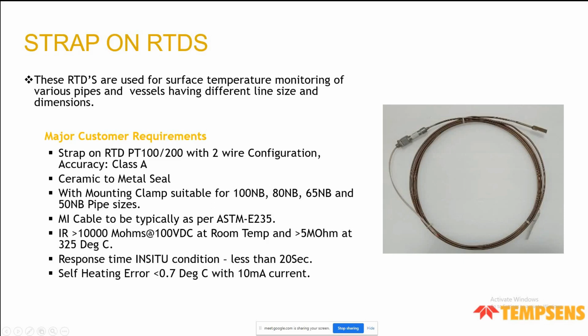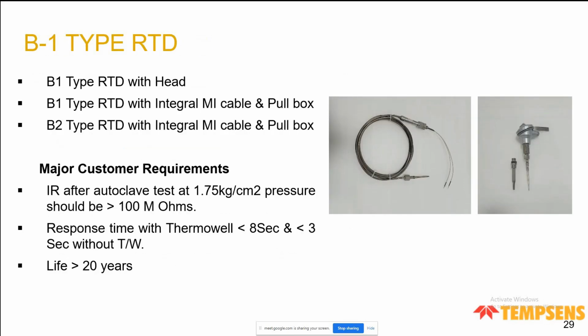The major point is that, with the pipe, the response time shall be less than 20 seconds. So you have to take care that there is no gap between the sensor and the outer pad, and the pad has to be cut properly so that it has maximum thermal conductivity with the pipe. All these things have to be taken care of for this customer. Mostly it is going to Nuclear Power Corporation, and we supply to all its plants in India. Then this is for measurement inside the pipe or some area. Here there is a thermowell, and there is an insert which goes inside the thermowell. These are called B1 and B2 RTDs. They can be with just the head or with the MI cable.